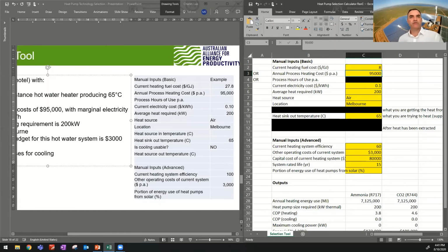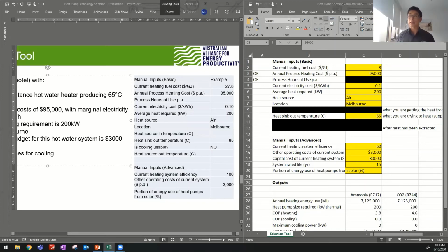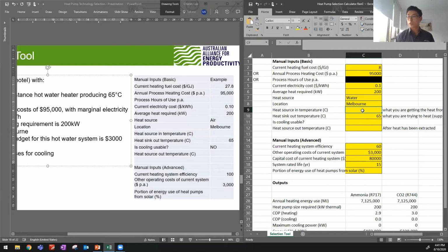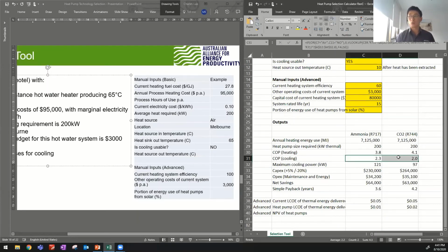Question: if you use AC chilled water as a heat source, do you give credit for the energy savings from reduced cooling capacity required from the AC chilled water system? Yes, you're basically using this heat pump as a chiller on the cooling side. So if I change the heat source to water, cooling it from 20 degrees to 10 degrees, this is essentially a refrigeration system, and it takes into account the COP of the cooling side. You'll notice this is far lower than a typical ammonia cooling system, because we're not just using the cooling - we're using the heating as the main application, and the cooling is just a benefit, so the COP on the cooling side is reduced as a result. But yes, you essentially get free cooling by producing hot water.